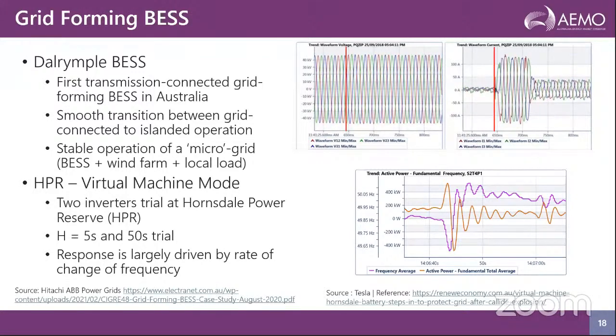Because it is a remote part of the network fed by a single radial line, if the line opens up, the battery would form an island with wind farm and the local load. And the wind farm capacity is quite large compared to the local load. So the wind farm would disconnect or reduce its output generation to meet the local load. So the figure on the top right shows that smooth transition. The red line is where the transition has occurred. And you can see that during the fault, it has provided a bit of a high current, and then it has stabilized and supported the local load.